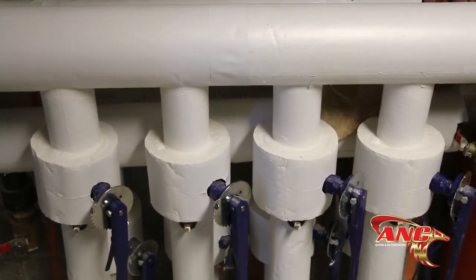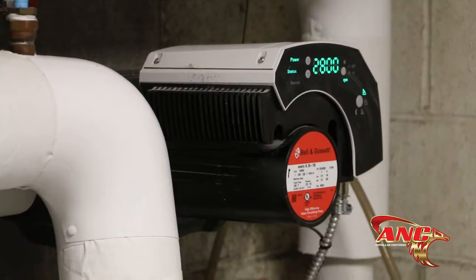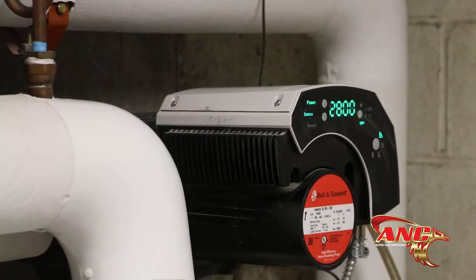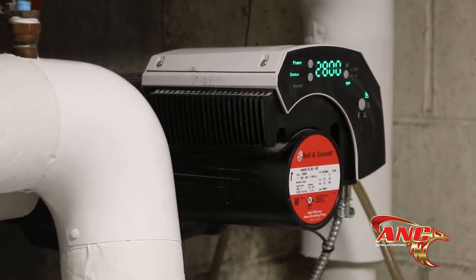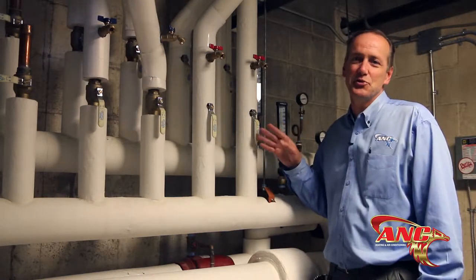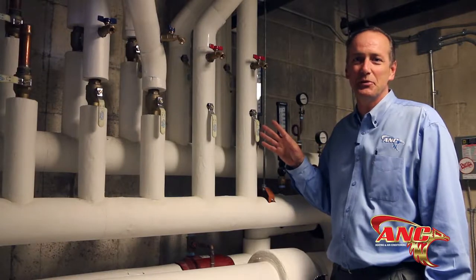This is what it looks like inside the building. We have our piping coming in, our high-efficiency variable speed pumps which ramp up and down based on the building load and how many heat pumps are calling. These were computer programmed — we hook a laptop up to them and program them. Here's the specific loop piping that goes out to the individual geothermal heat pumps spread throughout the whole facility to heat and cool the space.